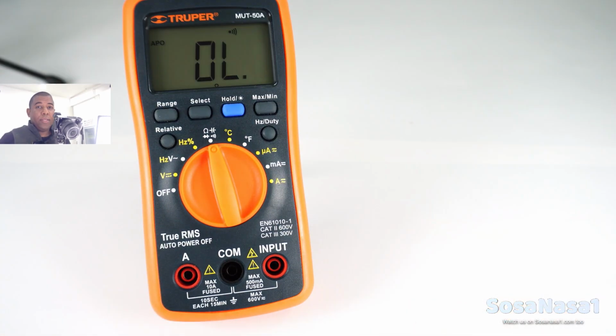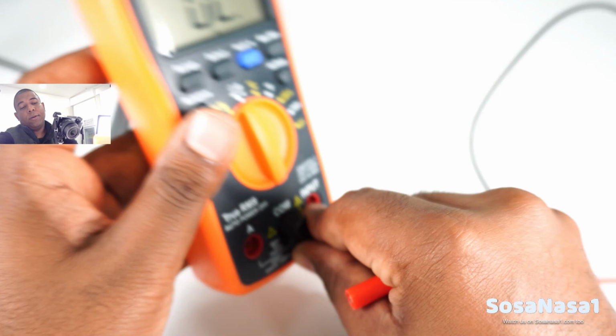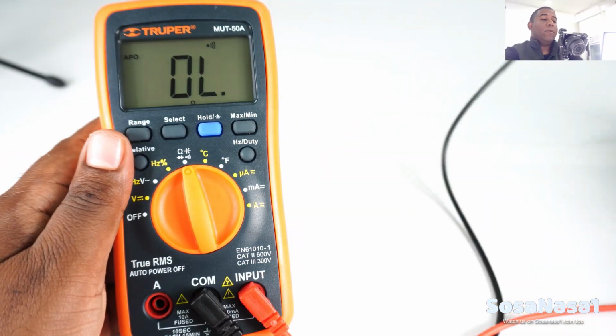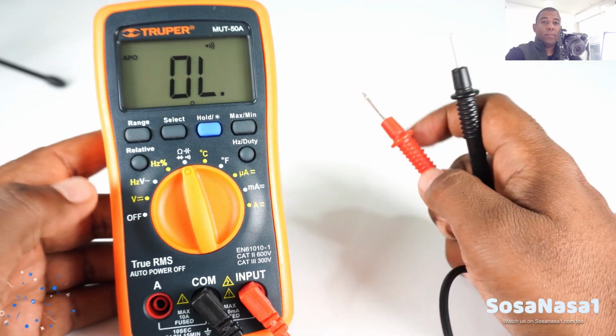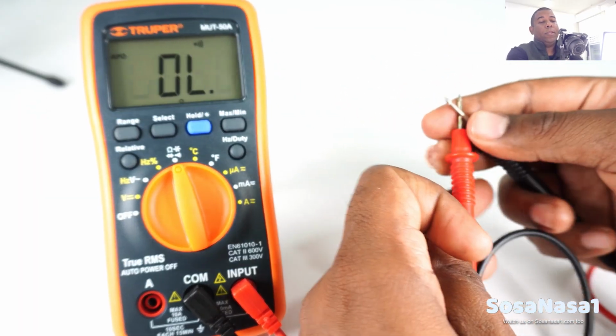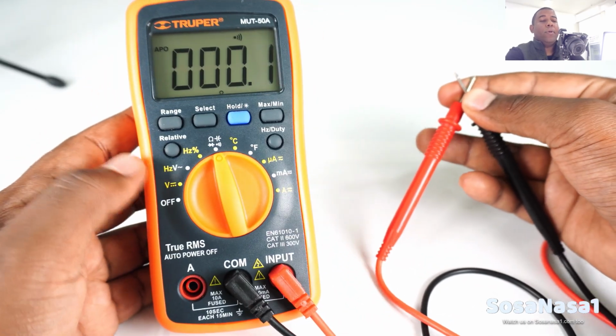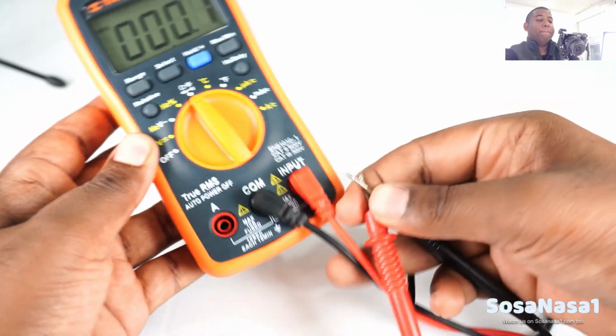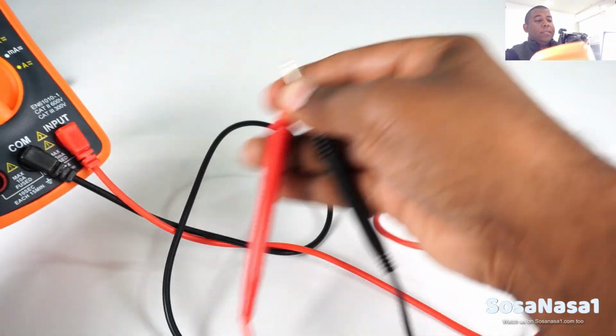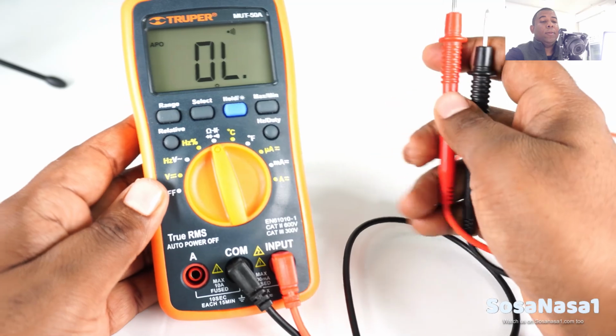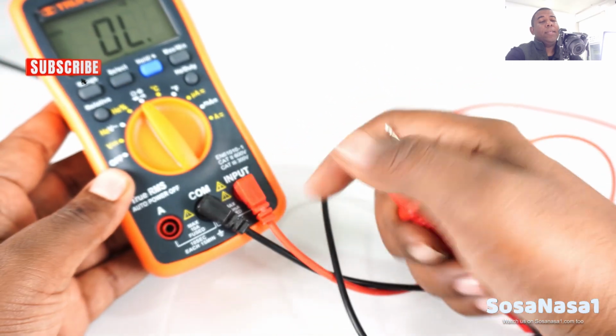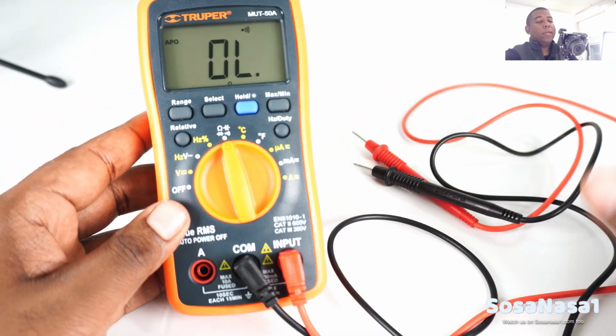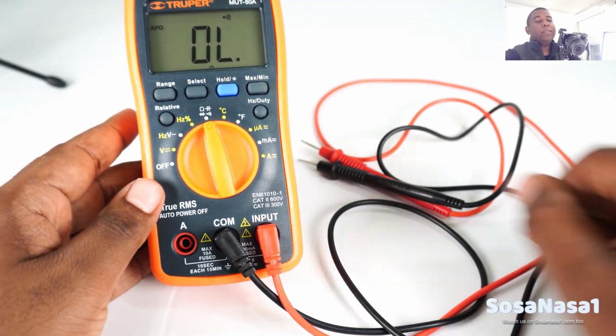Disconnect, and now repeat the same test with other test probe, like this. Connect here, ready, connect here, and now take the new ones and touch in this way. Now, like we are watching, in this case, these test probes are working correctly because the sound continues all the time. This means inside this cable isn't broken, like we are watching. These test probes are fine, are good in this case.